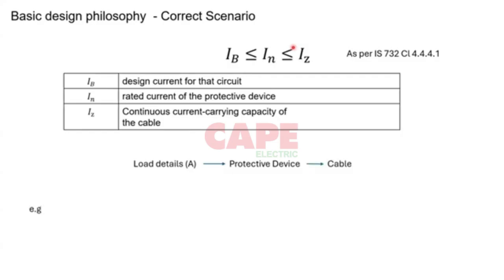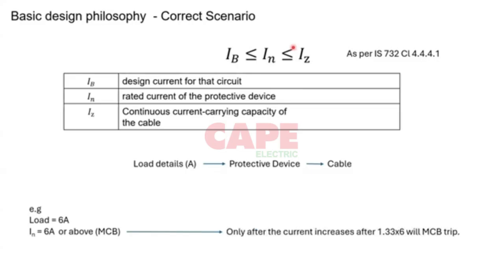Now, I'll give you an example. Suppose the load is 6 amps. If you're going to put an MCB, the rating can be 6 amps or above. You can ask why they put 6 amps, won't it trip? There are the conventional tripping time and non-conventional tripping time, with factors 1.33 and 1.45. Only after 1.33 times the rated current will the MCB start to trip, and at 1.45 times the rated current, 6 into 1.45, the MCB will trip within 1 hour. So that expression is there, and you can go with 6 amps or above.